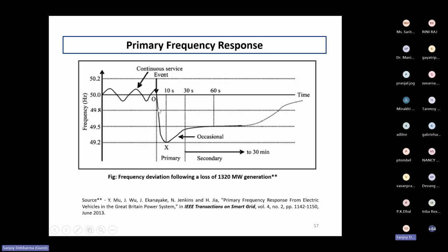But then when the ROCOF falls, you'll find it reaches this particular point because it was initially supported by its inertia, normally up to 5 to 8 seconds. After this inertia becomes zero—the kinetic energy stored in a rotating machine—the primary frequency control regulates and starts contributing to the grid through the primary governor response. The set point is updated, and the response moves toward the limits.